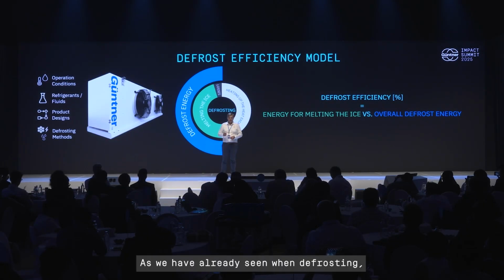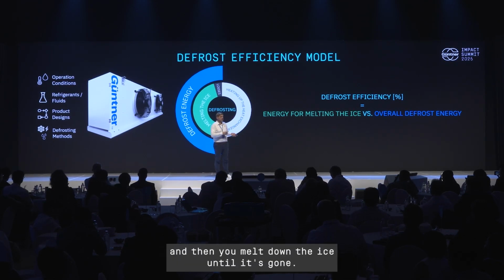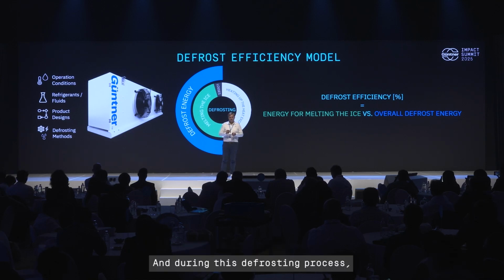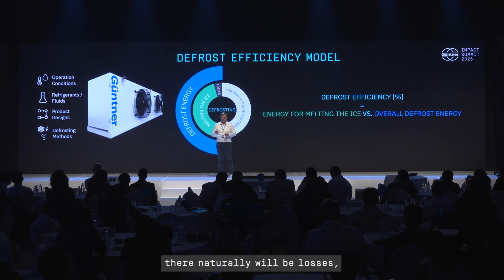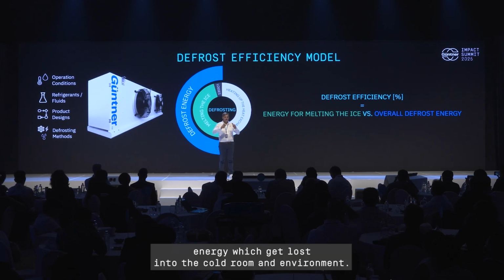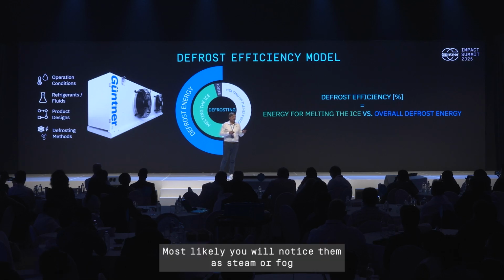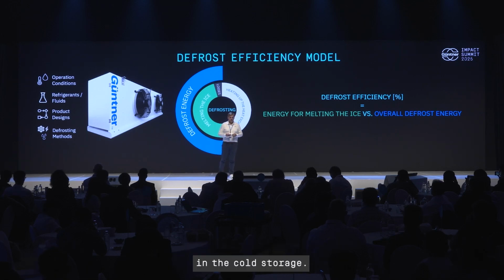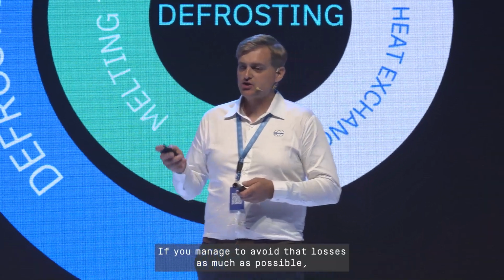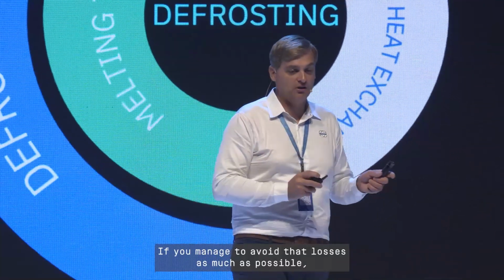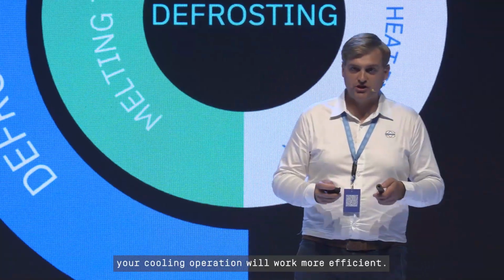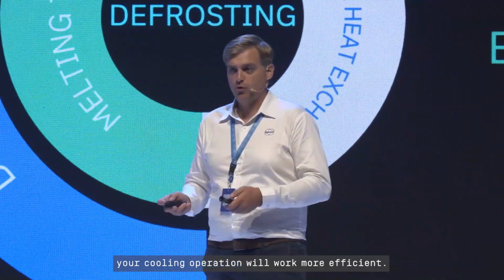As we've already seen, when defrosting you first heat up the heat exchanger and then melt down the ice until it's gone. During this process there naturally will be losses - energy lost into the cold room and environment. Most likely you'll notice them as steam or fog in the cold storage. If you manage to avoid those losses as much as possible, your cooling operation will work more efficiently.